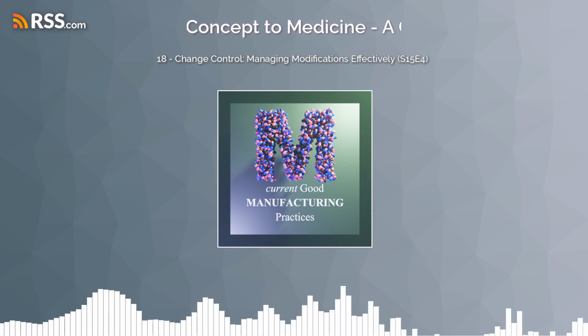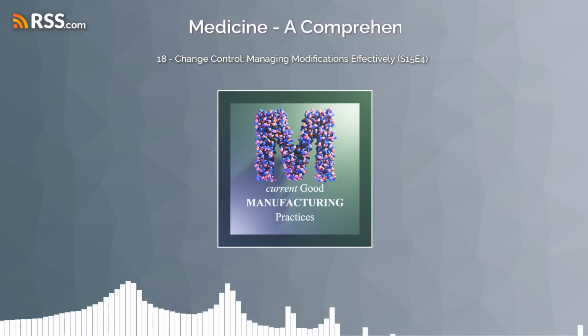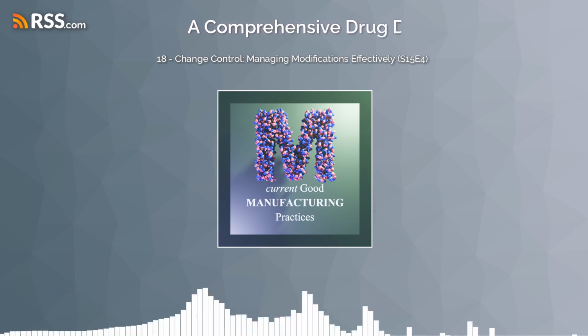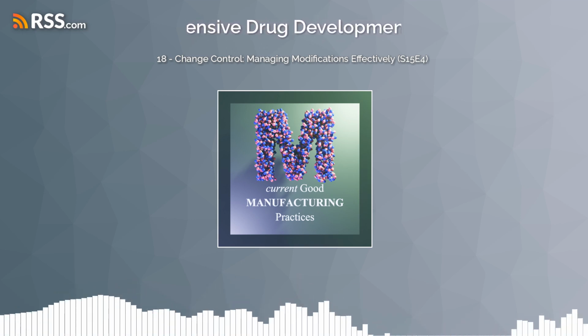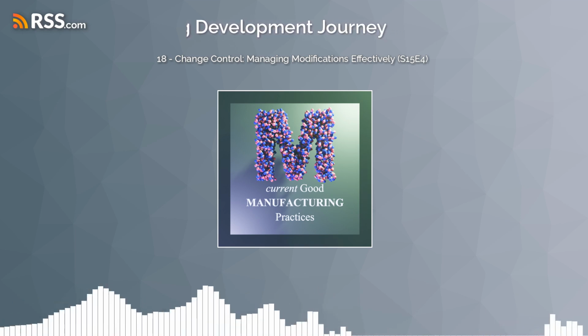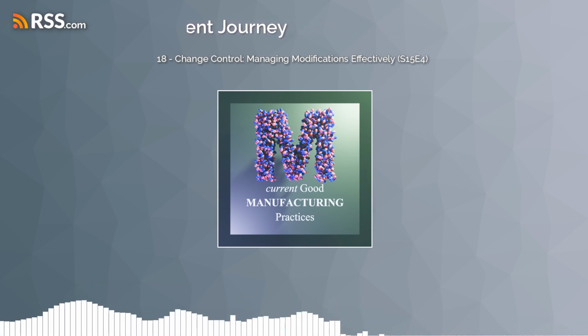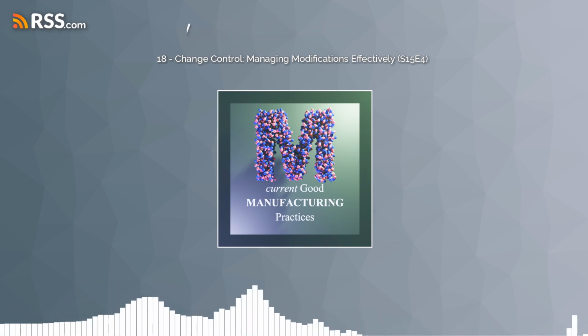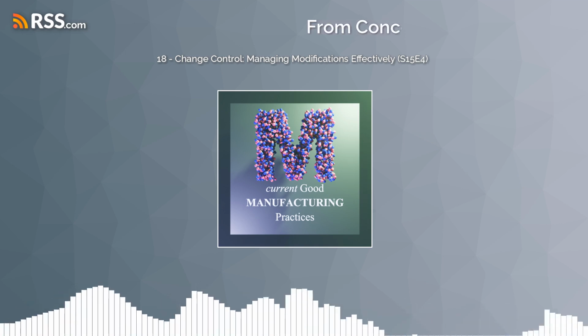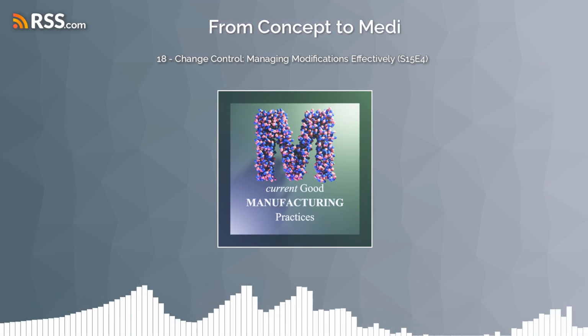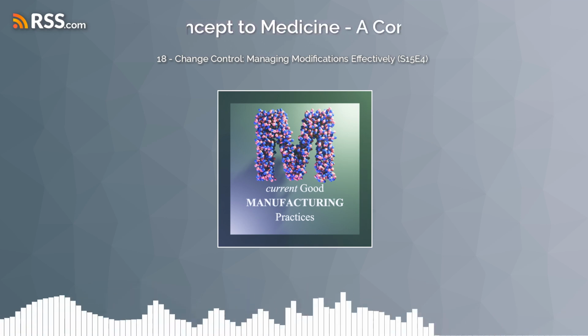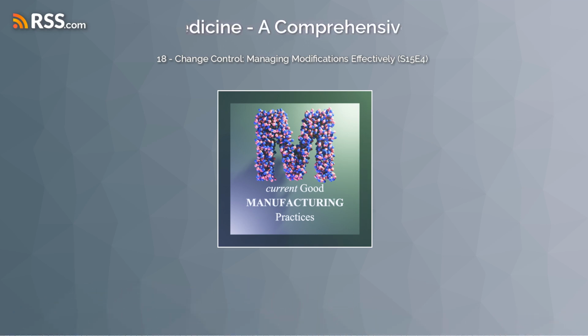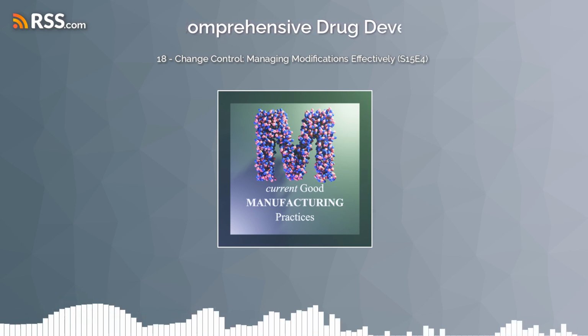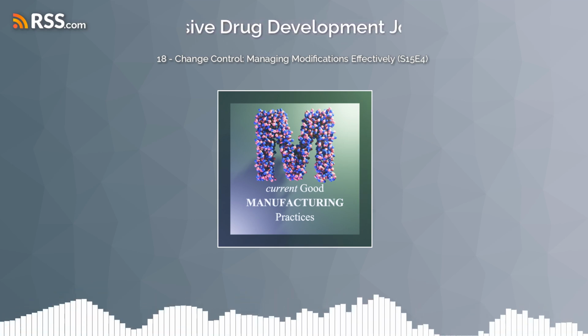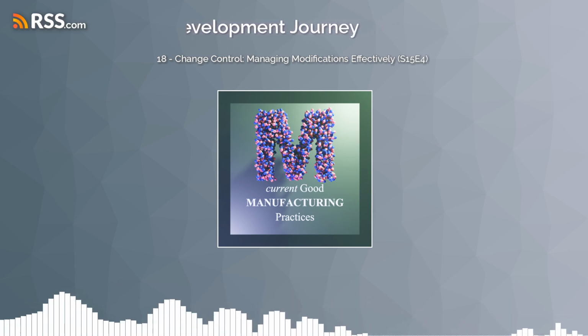Exactly. And equipment, that's another big one. You have to look at how the change affects the equipment itself, including its qualification and calibration. Remember that YouTube video on the GMP lab? They talked about DQ, IQ, OQ, PQ: design qualification, installation qualification, operational qualification, performance qualification. It was really interesting. They mentioned even moving an HPLC instrument a short distance could have an impact. Really? Yeah, like what if it's too close to an air vent? You might need to requalify it.